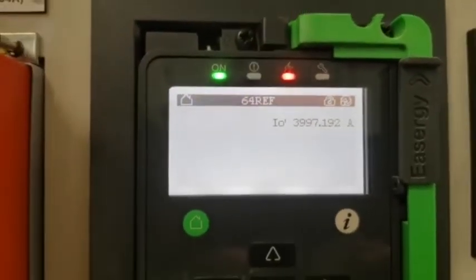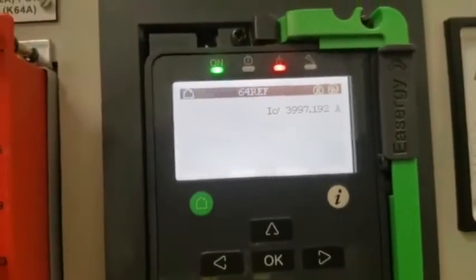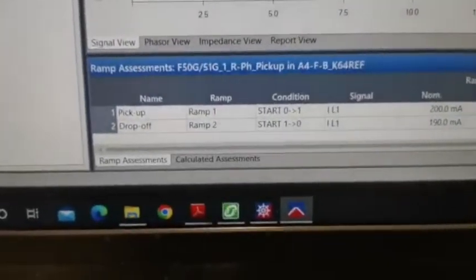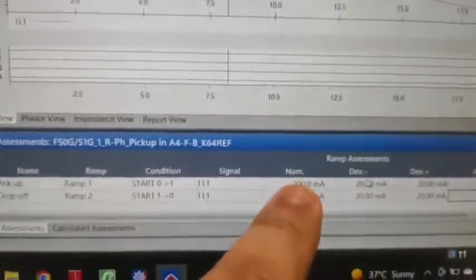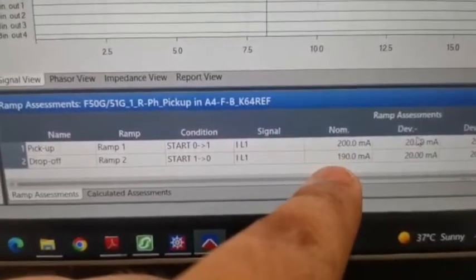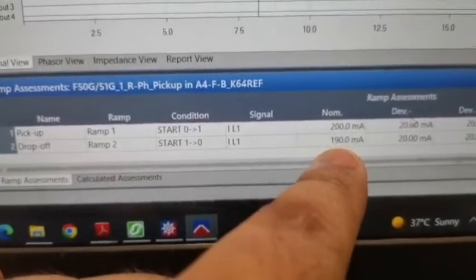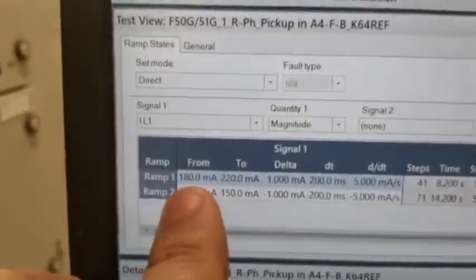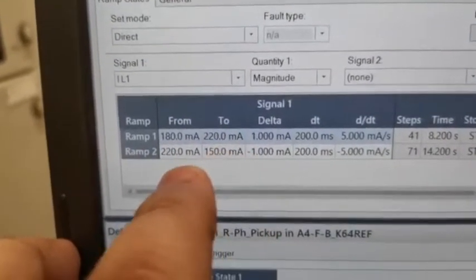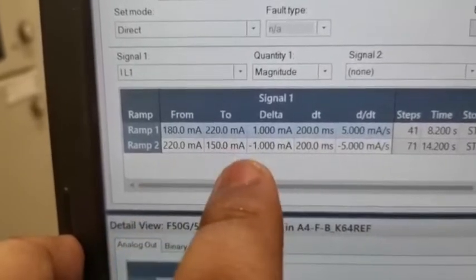Our REF fault setting is 0.2 amps — 200 milliamps — so our pickup is 200 milliamps. The dropout ratio is 95%, which means the dropout is 190 milliamps. We are gradually ramping from 180 milliamps up to 220 milliamps for the pickup test, and then from 220 milliamps down to 150 milliamps for the dropout test.